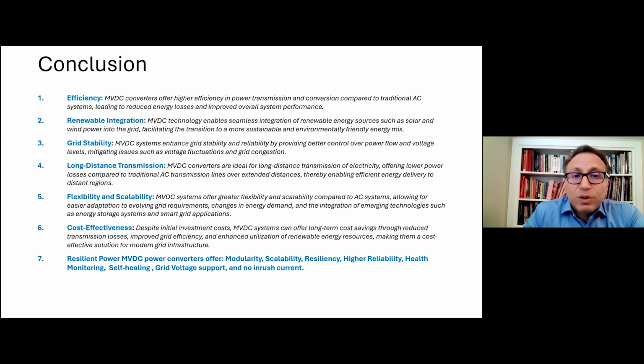It provides grid voltage support, such as reactive power compensation, and it offers no inrush current, which we know transformers do have. Take the problem in California, the Canyon fire, I guess, that was caused by PV inverters where one of them tripped and then, starting back, it required inrush current, overloading other power lines, and it created those problems. But this system does not have any inrush current.